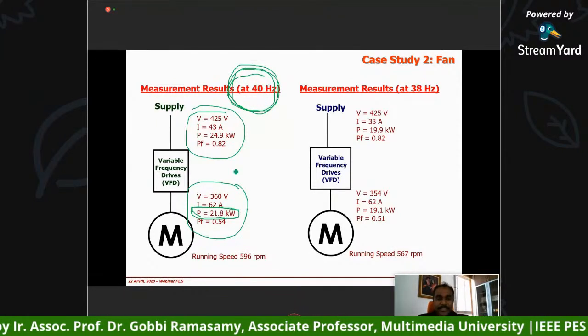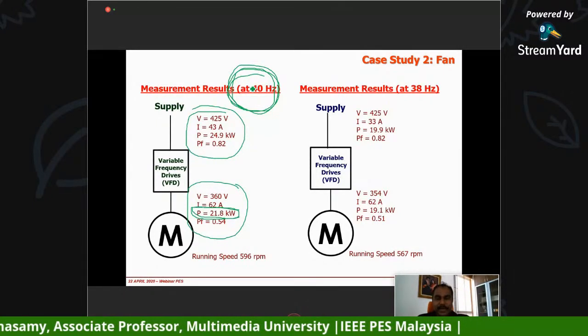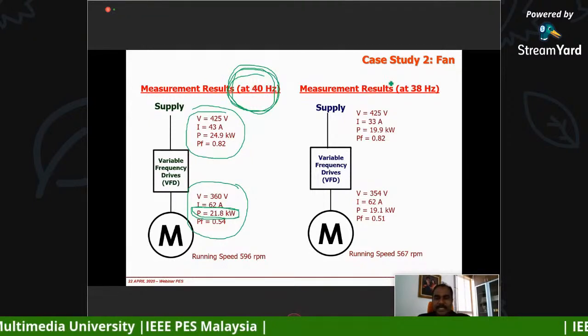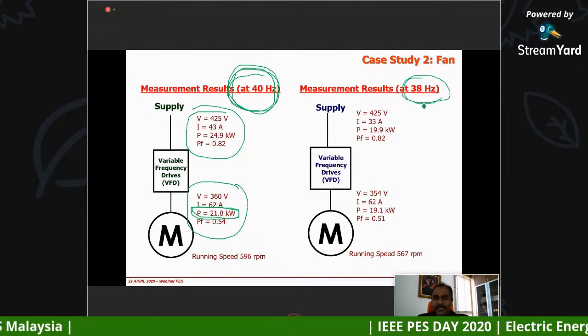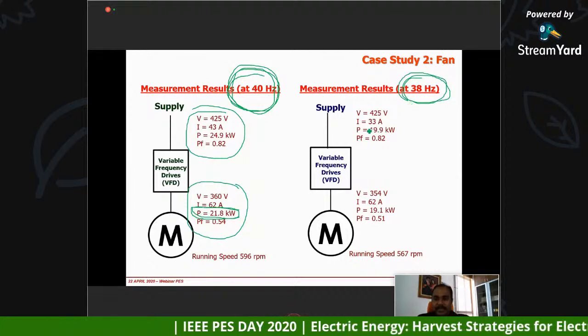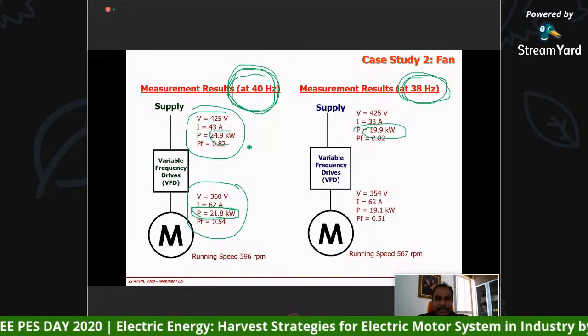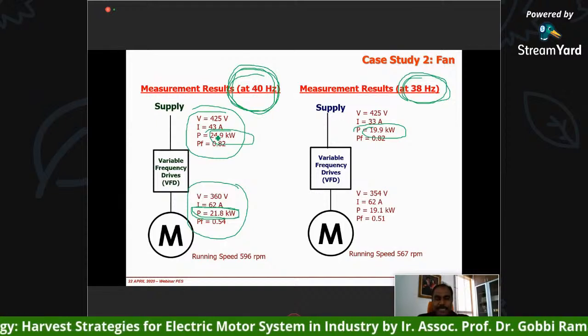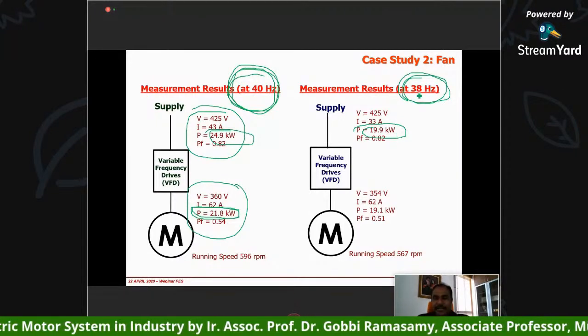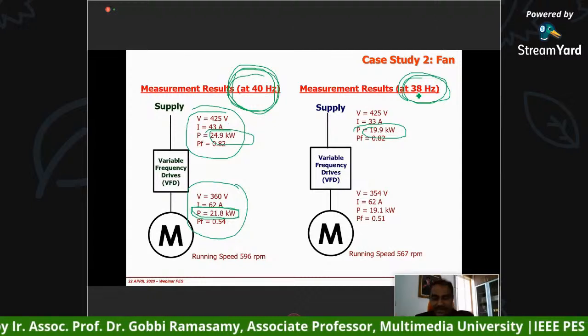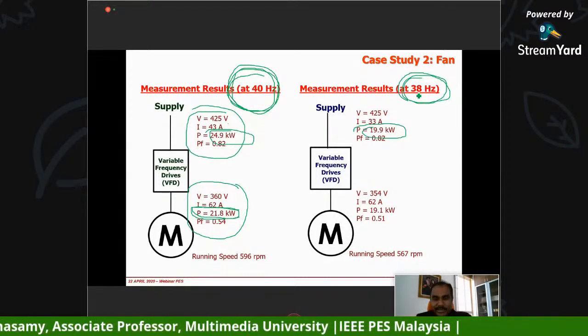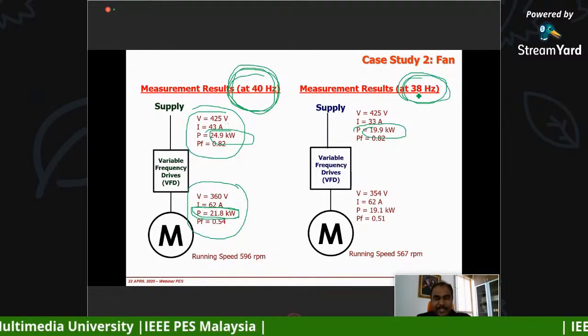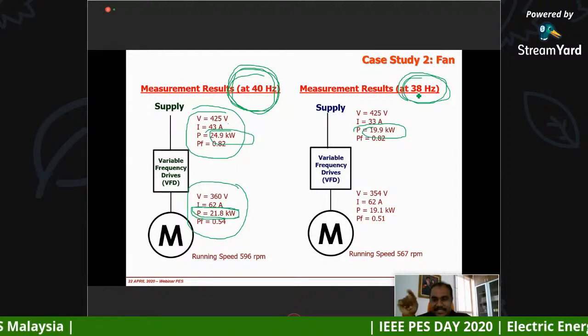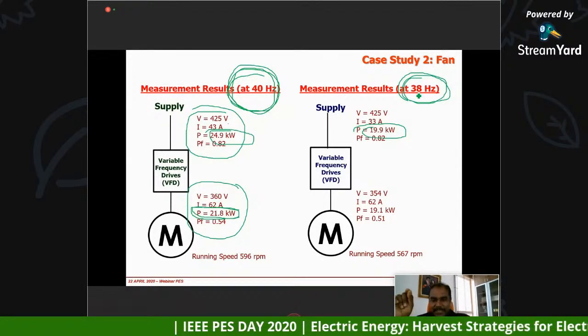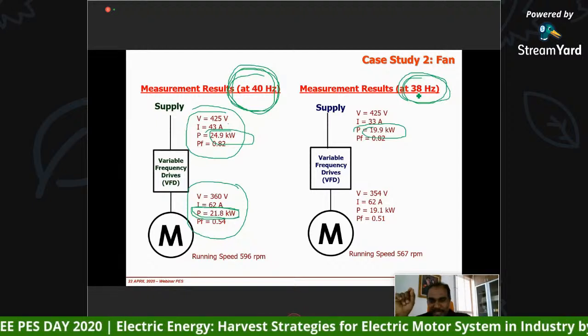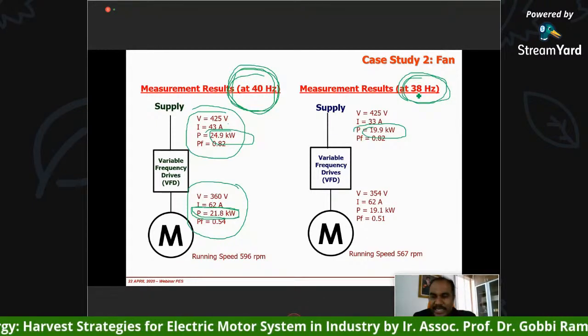Number two, it is always running at 40 hertz. So we said, okay, let's reduce the frequency by 2 hertz. Let's run at 38 hertz. And then we found, wow, look at the reduction of the power. From 24.9, it reduced to 19.9 just by reducing 2 hertz. That means in this case, there is no additional cost involved because the VFD is already there, the motor is already there. You just have to go there, do some simple settings, and reduce it by 2 hertz. And immediately you see that reduction in the power.